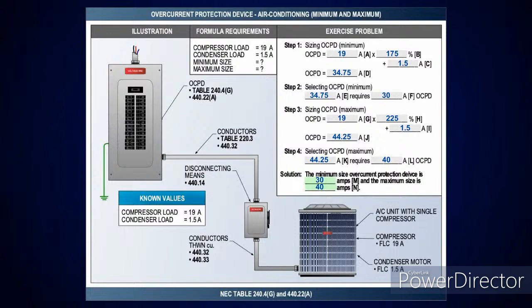Yeah, and what I think people aren't going to really understand about this too is you can't really see what's going on with the minimum circuit ampacity on this. And so that's where it's going to be kind of a little bit out of context, because you could have a minimum 30 and say, like, a minimum circuit ampacity of like 24 amps. And then you have your maximum at 40, it could be that same 24 amps. So you can do both of those with number 12 gauge THHN.